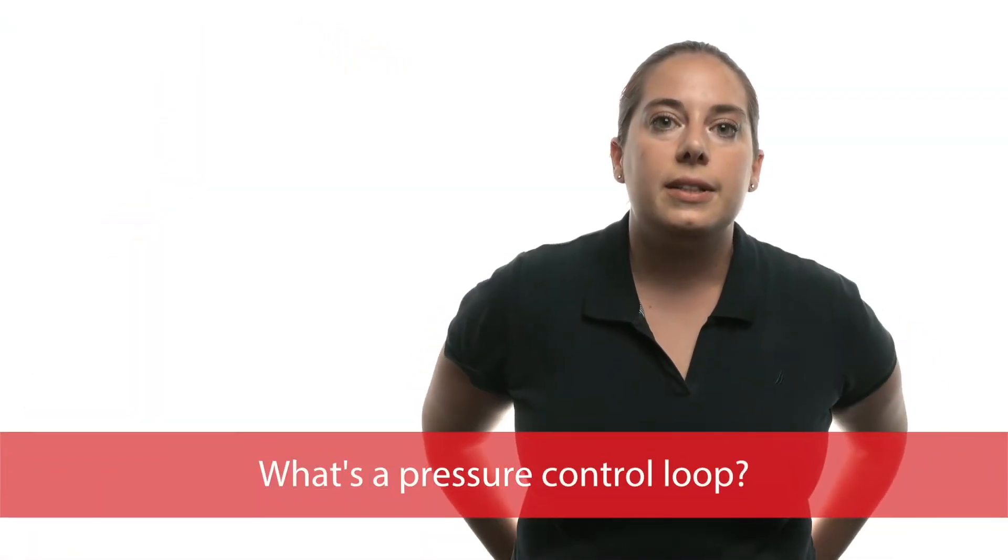So a pressure control loop, the nice thing about our mass flow controllers is that they measure four things. They measure volumetric flow rate, mass flow rate, temperature, and pressure. And you can control on any of those except temperature.